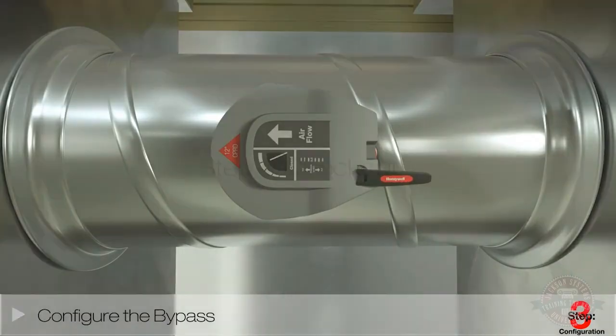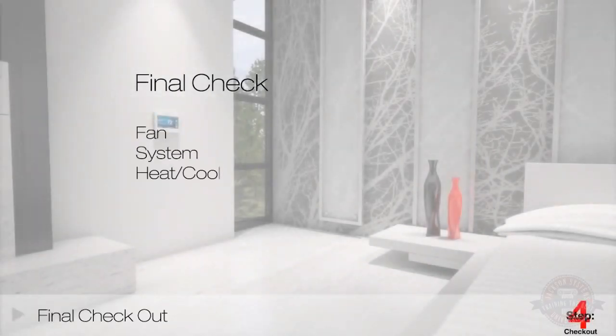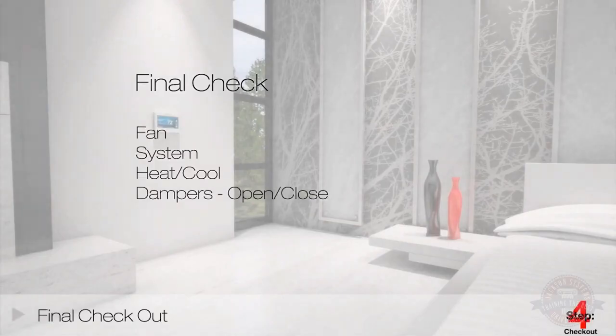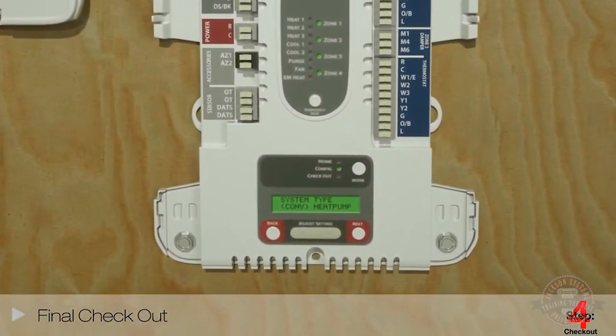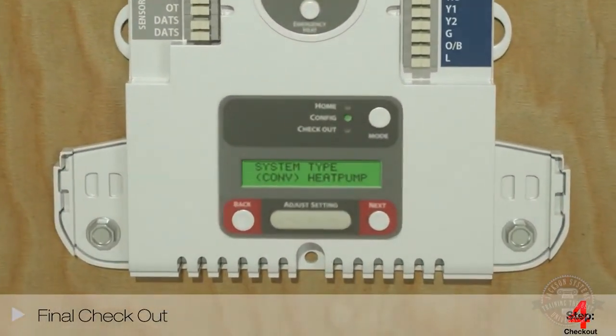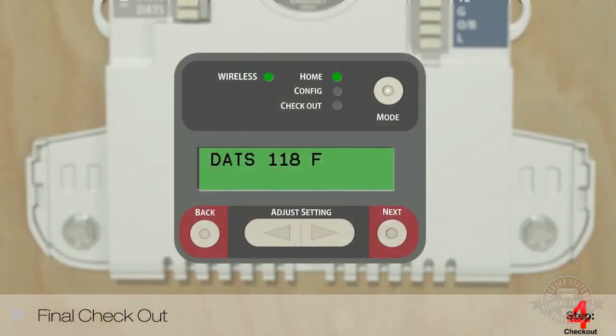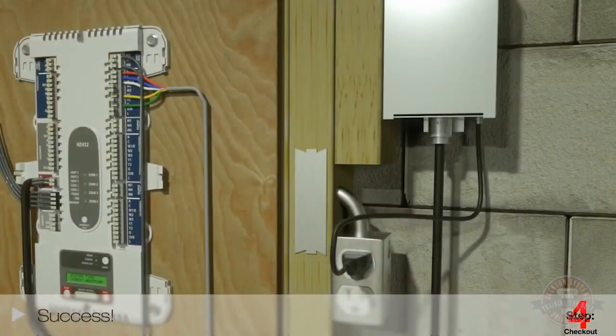Now it's time to perform a final check to ensure that everything is functioning properly, including the operation of the fan, system, heat or cool, and opening and closing the dampers. On the HZ432 and HZ322 panels, press the Mode button until the checkout LED lights up. This enables you to turn the HVAC equipment, heating, cooling, and fan on and off, as well as open and close the dampers for each zone.